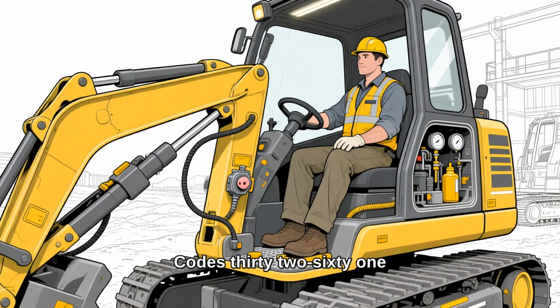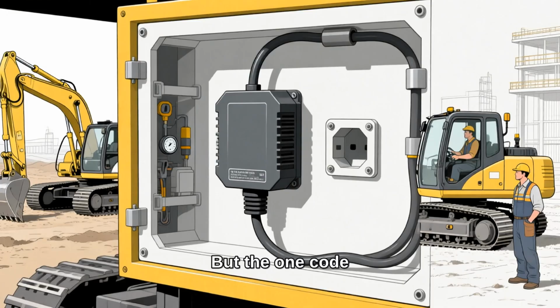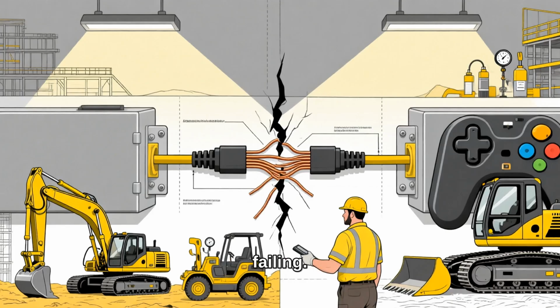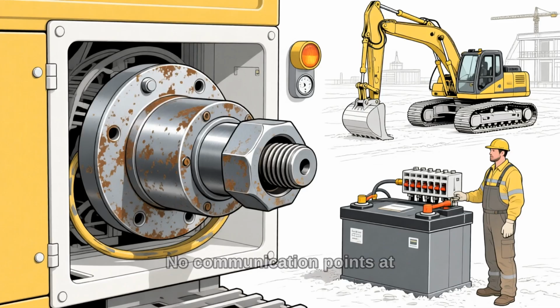Codes 3261 through 3264 cover the handle lock and pedal lock, short to ground, short to battery. Safety interlock wiring. But the one code in this family that stops everything is 3241, no communication. That's not one part failing, that's two computers that stop talking mid-sentence, like a call dropping at the important word. No communication points at power, grounds, or the main link between controllers. Check those before you ever condemn a controller.